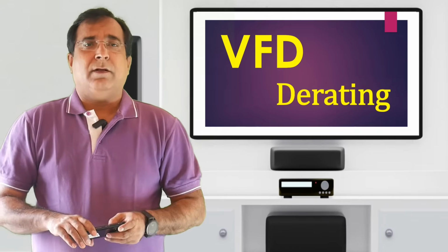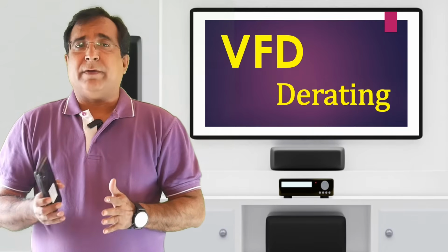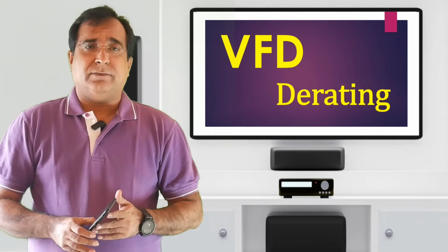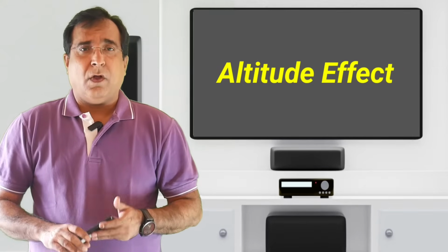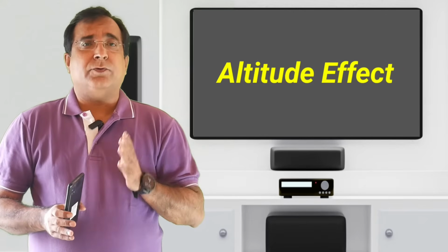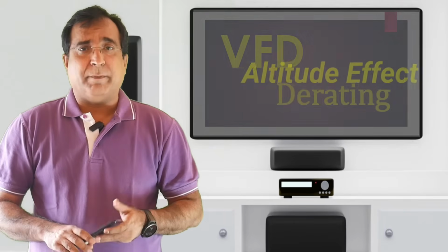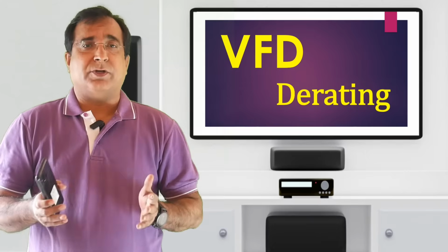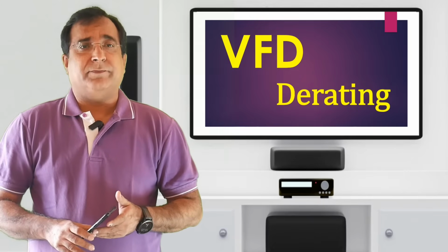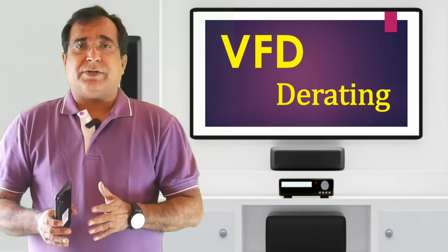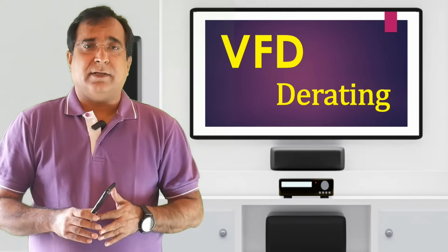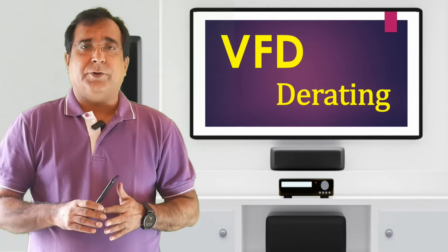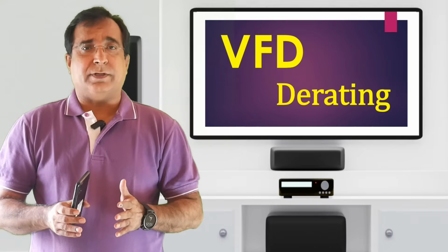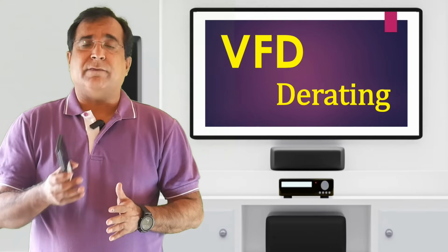Got it? Let's look at the reasons why VFD actually needs to be derated. First one is altitude effect. What happens when a VFD is taken above sea level? I mean when installed in hilly areas or some location that is higher than sea level. Atmospheric air pressure is found to be less in hilly areas than at sea level, due to which the density of air reduces, which means the air becomes thin.